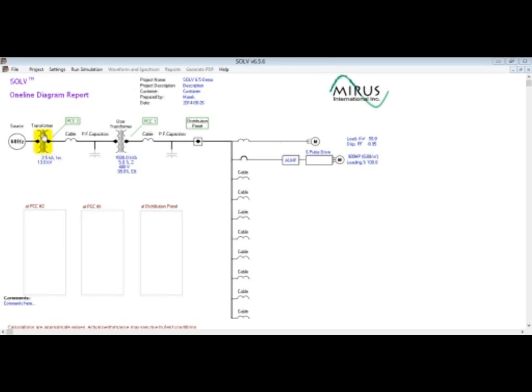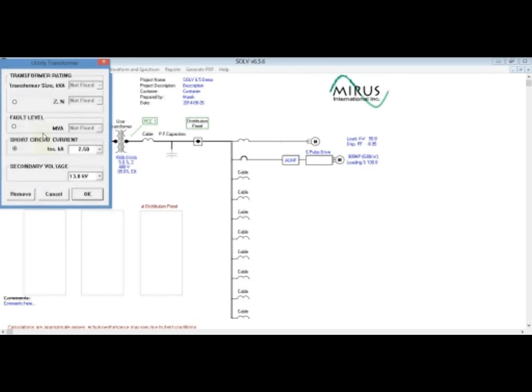So with the utility transformer highlighted, left click opens the selection window with transformer ratings and system voltage. There are three ways to define the utility source. Most often you will enter transformer size, kVA, and percent impedance. But when this is unavailable, utility fault level in either MVA or short circuit current in kiloamps can be entered instead. For this simulation, I'm using short circuit current 2.5 kA and secondary voltage 13.8 kV. If the utility information is not available, simulation can be performed without entering the source information.